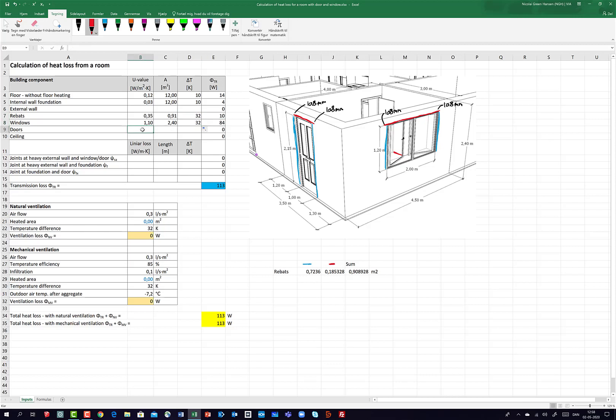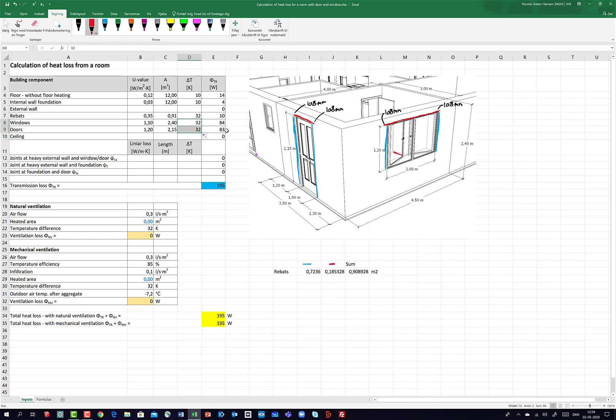Then I take the door. Again, you look up the U-value on the producer's website — it depends on the materials and also whether you have glass in the door. For the window too, the U-value can vary depending on how many layers of glass and the frame-to-glass ratio. I put in a fictive value of 1.2. The area of the door is 1 meter wide times 2.15 meters high. The temperature difference is again 32 Kelvin, giving 83 Watts heat loss.